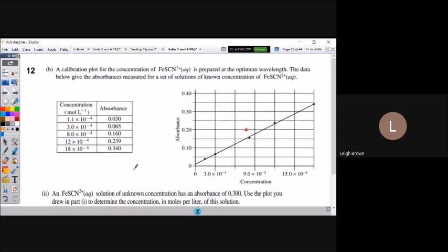We're supposed to wipe it off with a little chem wipe so that no fingerprints inhibit the light from getting through. So when you have an absorbance that's too high, it could be because it wasn't cleaned properly when it was put into the instrument. Maybe there were fingerprints preventing the light from getting through, so it had a higher absorbance than expected.